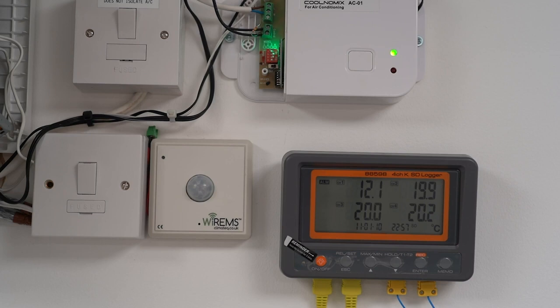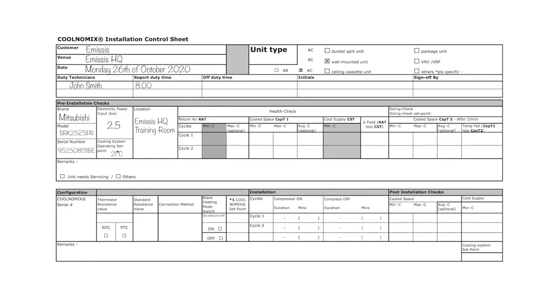During the health check, we record using 3 temperature probes with min-max capability. We record return air temperature, cool space temperature, cold supply temperature. Calculate the delta T of the minimum return air temperature and the minimum cold supply temperature.